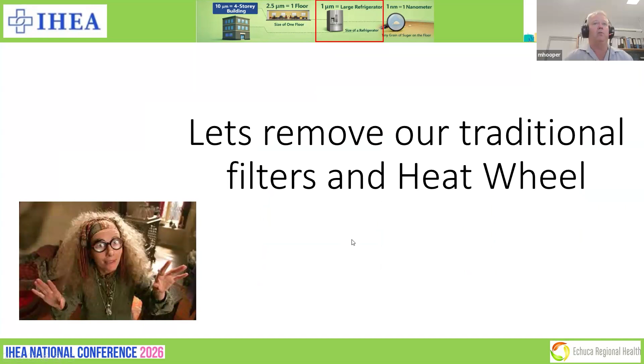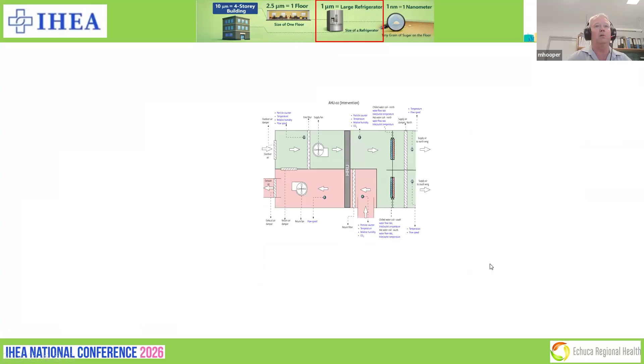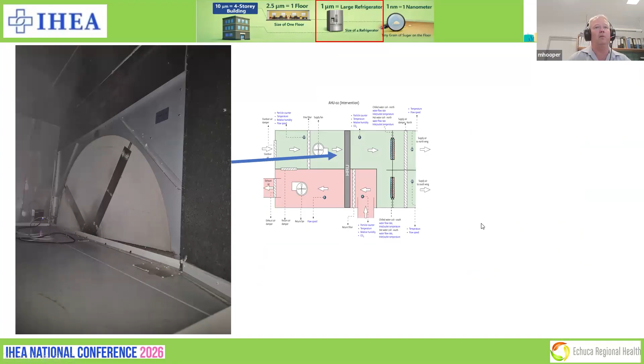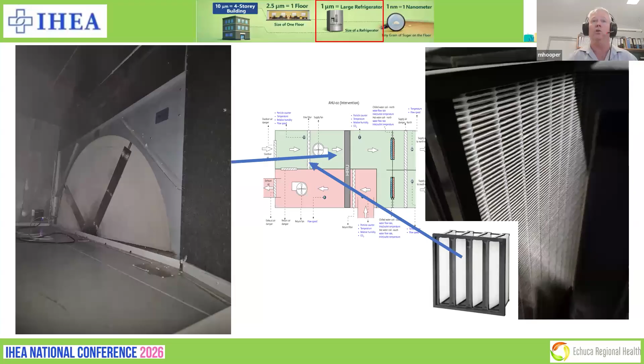So we remove our traditional heat filters and our heat wheel, and we did some measurements. So this is a before picture, and so you can see the heat recovery unit that was in that plant, and then that's the type of F9 filter we looked at before. That photograph there is actually of that F9 when it was pulled out. It was 2 years old and still looked like it was fresh out of the box. So they've been doing a pretty good job, which was great to see.